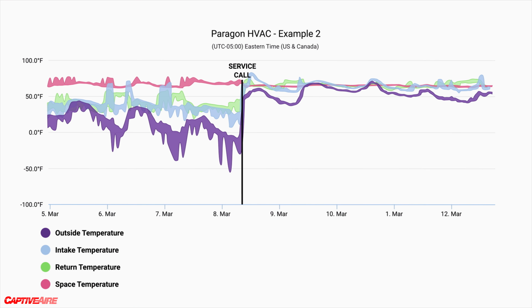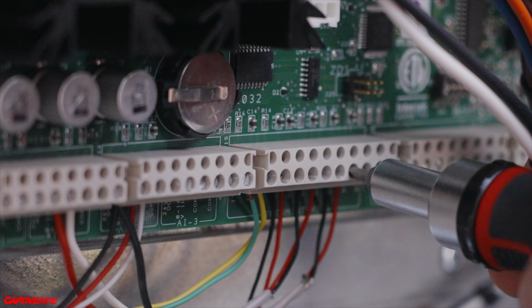We saw going into it, go out, check this. They changed the wiring in the field, and you can see the temperatures all came right back into where they expected once he made that change. So unless you're going through and actually reading that temp reading in the field, this would have been a very difficult thing that probably would have taken a few hours for a tech to diagnose versus it took them 2 minutes to go out, look for this, flip the wires back, and fix it.